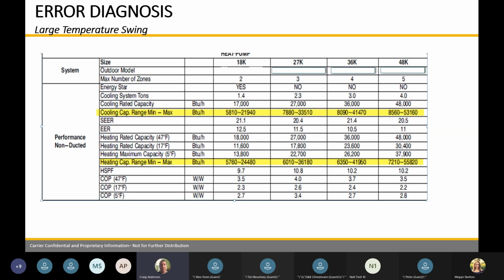So you'll notice on our units, the turn down ratio on an 18 is 58, and it'll actually heat or cool up to 21,940. So an 18,000 is actually a 22,000 BTU unit. So things to look at: did they need a 24 or anything like that? The 18 might have been big enough because it can actually cool what it needs or heat what it needs. It'll heat to 24,000 BTUs. So did you need to go to a 24? Your turn down ratio on an 18 is less than your 24. So those are things to look at for large temperature swings.